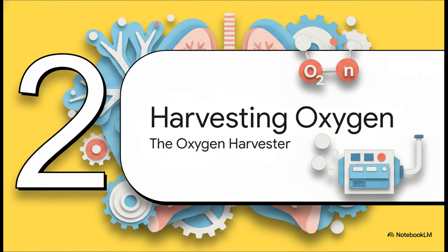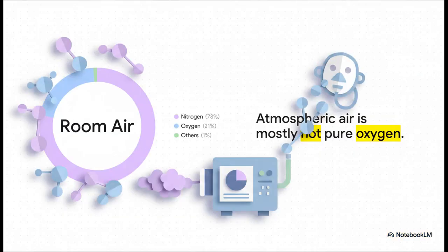Section 2. Harvesting pure oxygen. When the biological machine is starving for oxygen, that's when we bring in the oxygen concentrator. And the fundamental problem we're trying to solve here is actually surprisingly simple. Atmospheric air is mostly not oxygen. Room air is roughly 78% nitrogen and only about 21% oxygen. So, to help a struggling patient, we can't just blow more regular room air at them. That's not going to cut it. We actually need to actively harvest the oxygen out of the air.